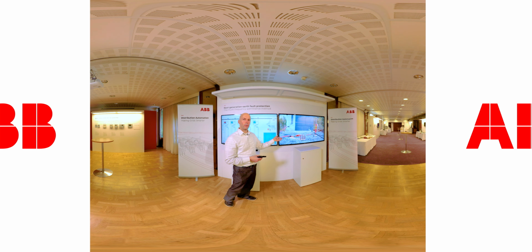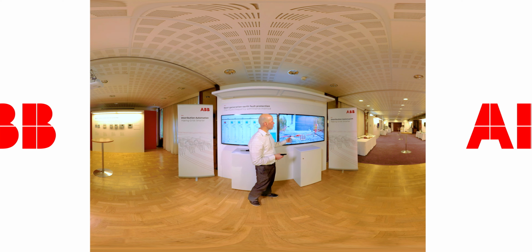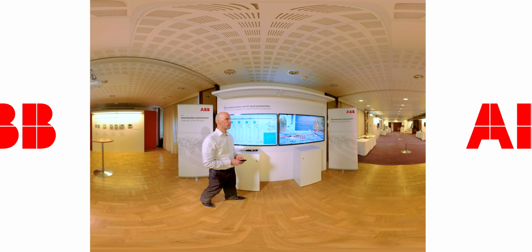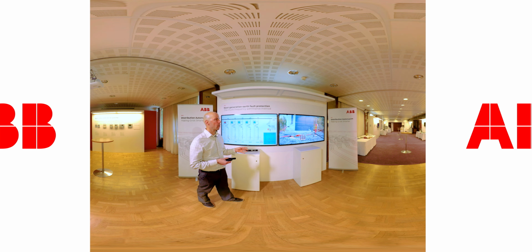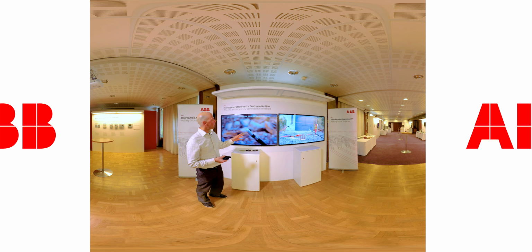So here you see how we conducted a restriking earth fault test in this network. And such a fault is known to be very problematic with conventional, traditional protection algorithms, especially when they are based on fundamental frequencies, such as the I0 cosinus method.